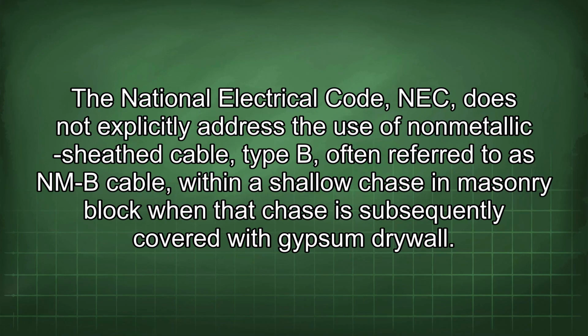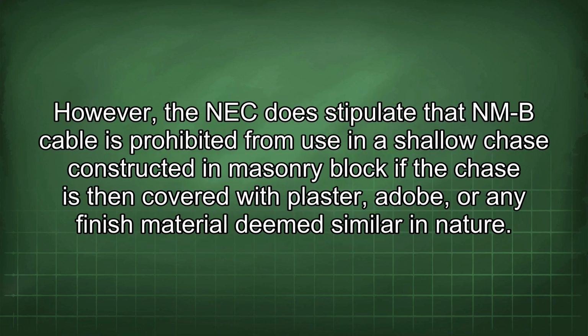The National Electrical Code (NEC) does not explicitly address the use of non-metallic sheathed cable type B, often referred to as NMB cable, within a shallow chase in masonry block when that chase is subsequently covered with gypsum drywall. However, the NEC does stipulate that NMB cable is prohibited from use in a shallow chase constructed in masonry block if the chase is then covered with plaster, adobe, or any finished material deemed similar in nature.